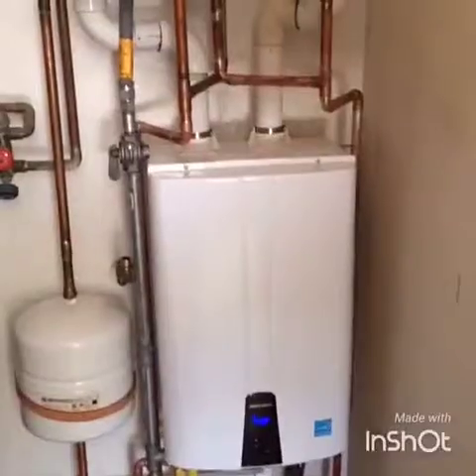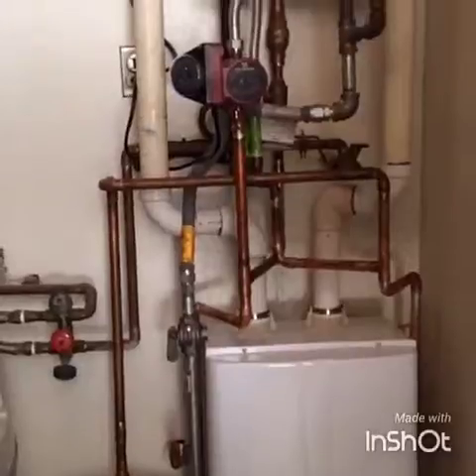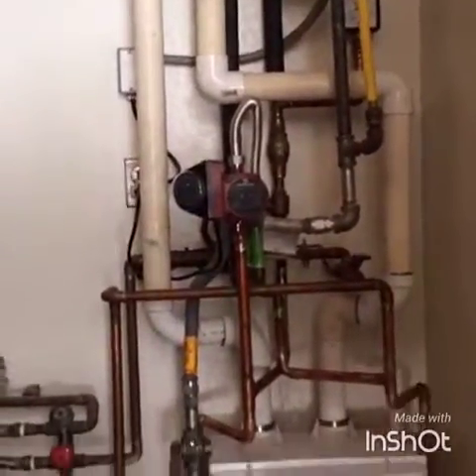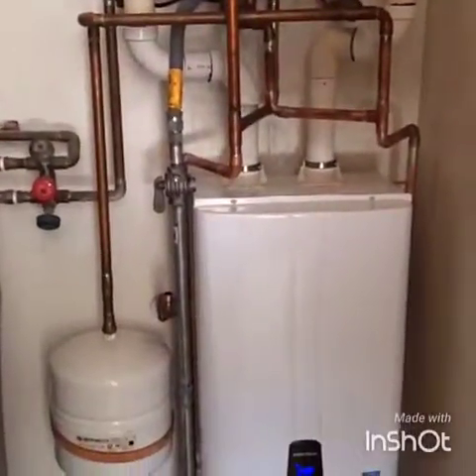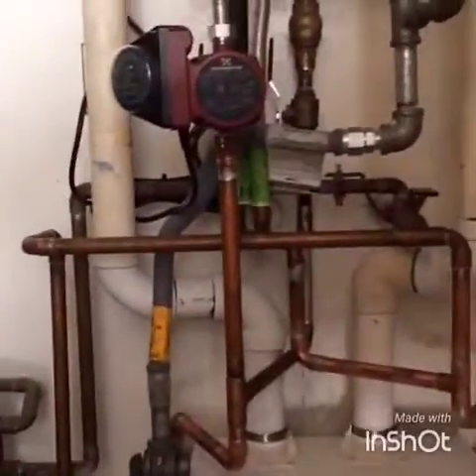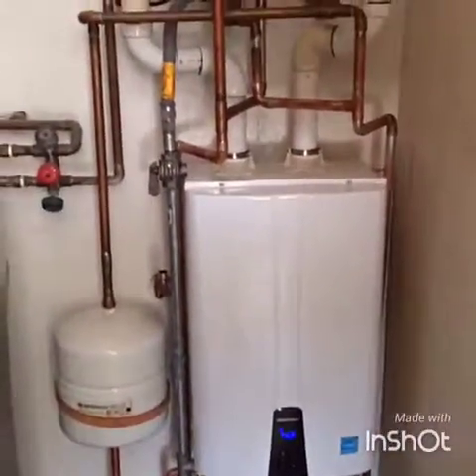We're going to hang the Navien. We're complete — the Navien NPE-248 is all piped in: gas, flue functioning, set at 140 degrees. It's got an internal recirc pump and an external recirc pump, and we've got hot water. My wife is happy. Looks like a pretty clean job, no leaks. Good job, Lou.